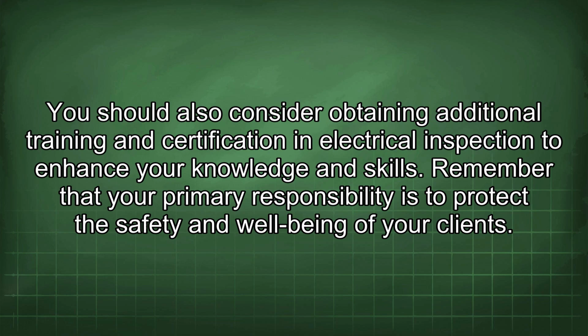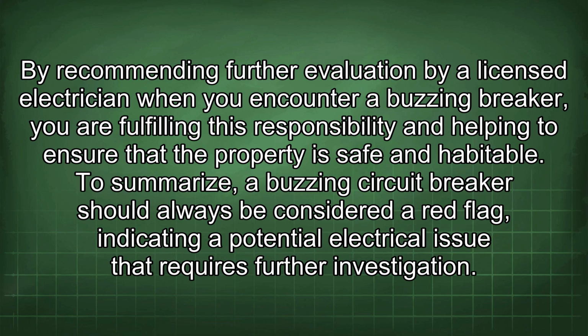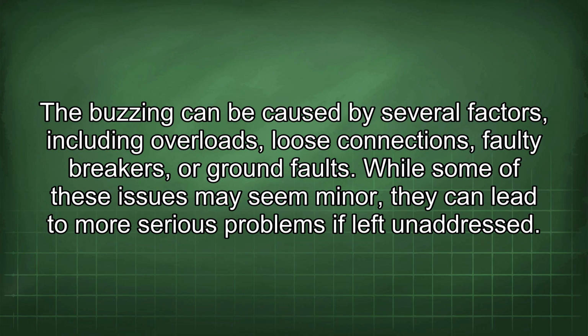Remember that your primary responsibility is to protect the safety and well-being of your clients. By recommending further evaluation by a licensed electrician when you encounter a buzzing breaker, you are fulfilling this responsibility in helping to ensure that the property is safe and habitable. To summarize, a buzzing circuit breaker should always be considered a red flag indicating a potential electrical issue that requires further investigation. The buzzing can be caused by several factors, including overloads, loose connections, faulty breakers, or ground faults.